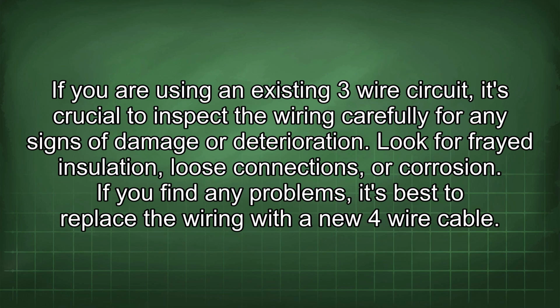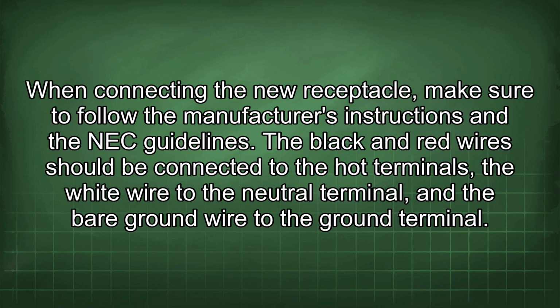If you are using an existing 3-wire circuit, it's crucial to inspect the wiring carefully for any signs of damage or deterioration. Look for frayed insulation, loose connections, or corrosion. If you find any problems, it's best to replace the wiring with a new 4-wire cable. When connecting the new receptacle, make sure to follow the manufacturer's instructions and the NEC guidelines. The black and red wires should be connected to the hot terminals, the white wire to the neutral terminal, and the bare ground wire to the ground terminal.